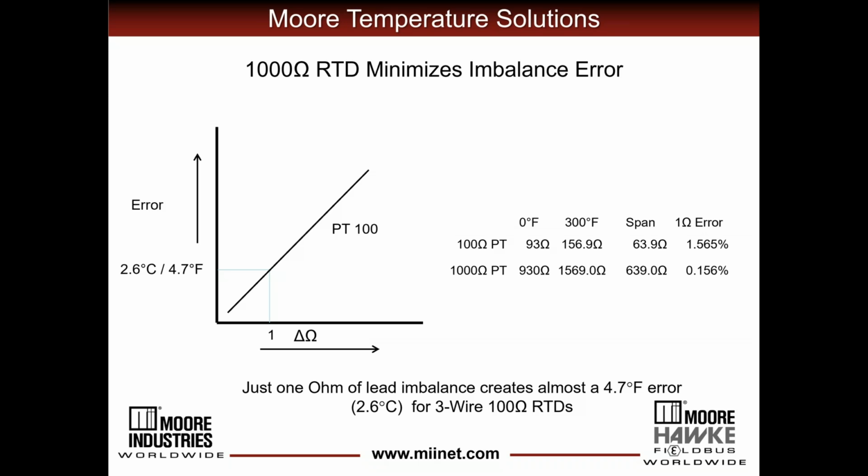All right. Question from Pat. Will regular terminal blocks in the wiring path cause errors in measurement? Well, not if the screws, okay, so are we talking about RTDs? Sure. Thermocouple? Sure. Generally not, unless you're using a 3-wire RTD and one screw is tighter than the other screw. Essentially, the wire gets hardened over time and the resistance changes.